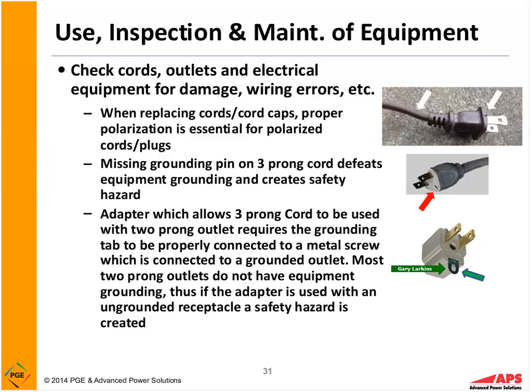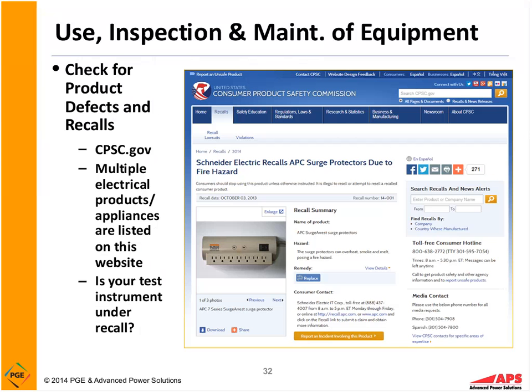A lot of people get shocked and killed with the use of portable cords and tools. So it's also important that we pay attention to product defects, whether it be, in this case, a surge suppressor that's catching on fire, or a meter. So in other words, if you're using test equipment to meter, to measure voltages, or to verify lockout tagout, there are a lot of meters that are under recall. When is the last time you checked to see if your meter is under recall?